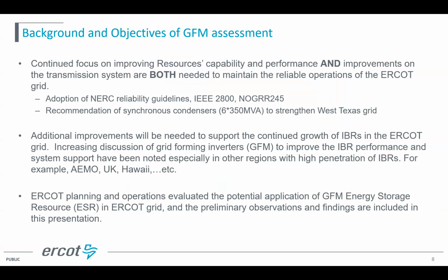So we will continue to improve resource capability and performance, such as adopting the NERC reliability guideline, IEEE 2800, and also ERCOT NOGRR 245, basically to require the units to stay online. At the same time, we try to improve the transmission grid as well. For example, we recently recommended 6 synchronous condensers in West Texas, together 2100 MVA, to strengthen West Texas. So we need both the generation side, or IBR side, and also the transmission system side to maintain reliable operation of the ERCOT grid, but we feel this is probably still not enough.